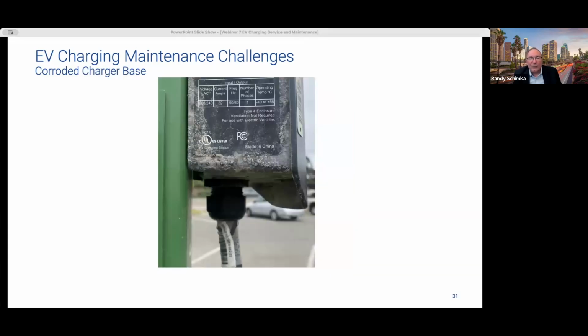This photo shows a charger on a pedestal post with visible corrosion or water damage at the base. So there's some kind of a moisture or leak issue here. Corrosion can degrade the charger's structural integrity and electrical components and can lead to a malfunction or outright failure of the charging station. So you want to use corrosion resistant materials for outdoor chargers and ensure proper sealing or drainage on the cases to prevent moisture buildup.